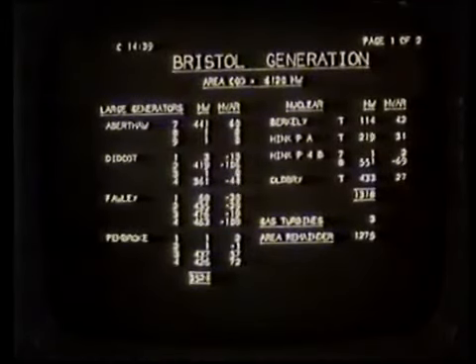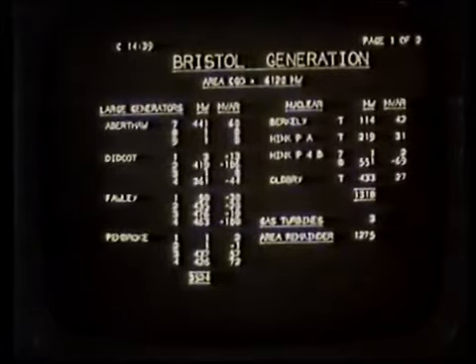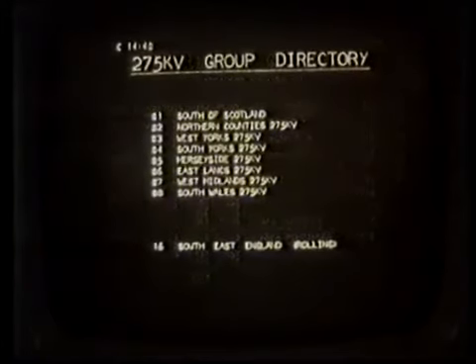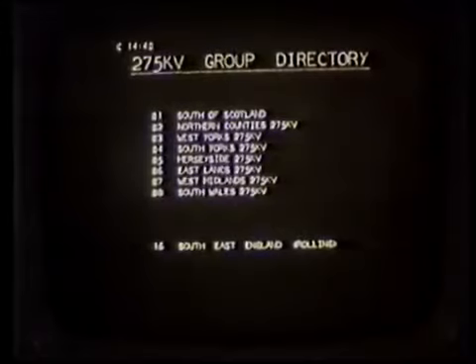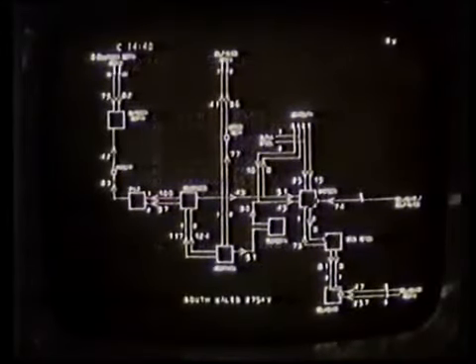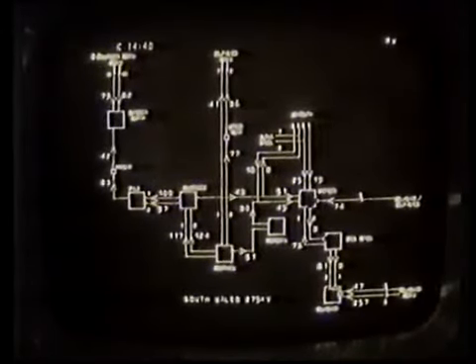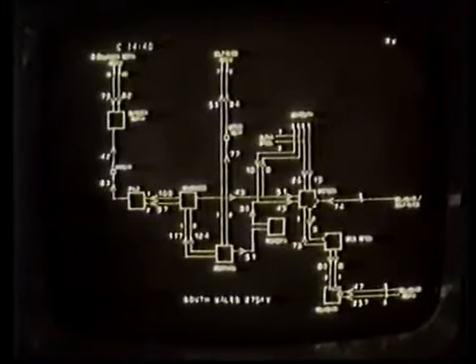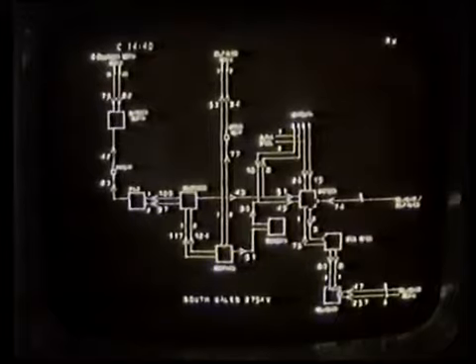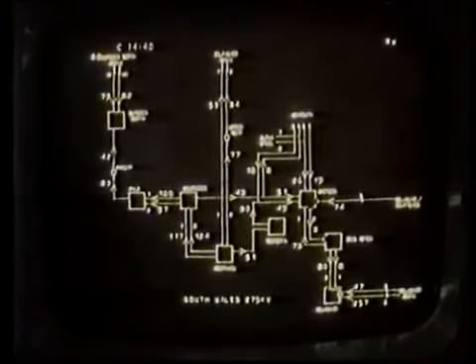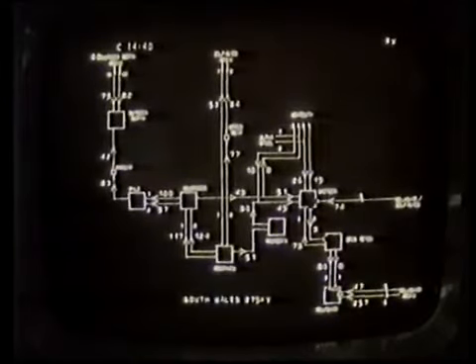Alternatively, he can reconfigure the network. That is, he can change the arcs which join one vertex or substation to another, and the switches at the substations enable him to do this. But if he changes the configuration of the network, where then are the critical arcs, that is, the lines likely to become saturated in the event of a line failure?